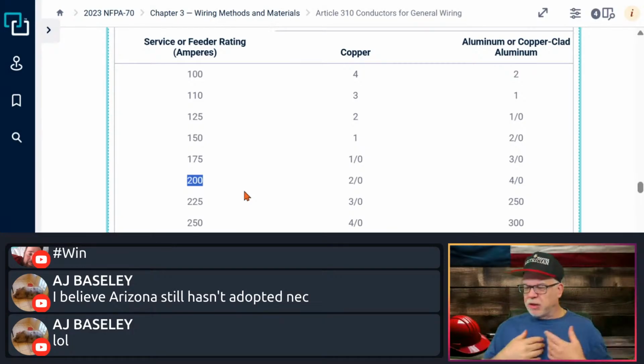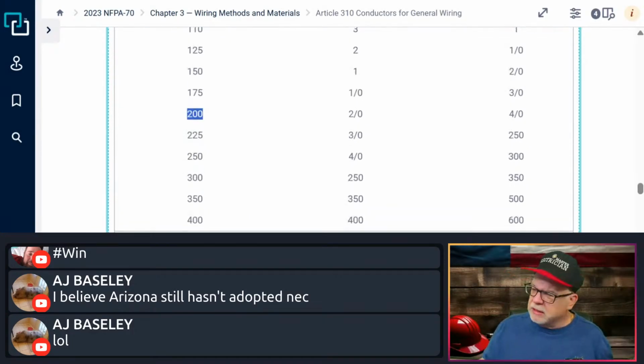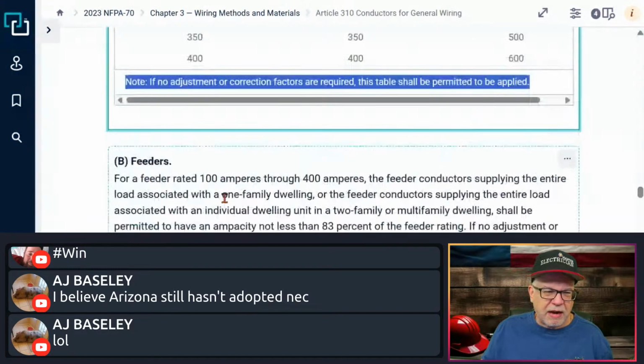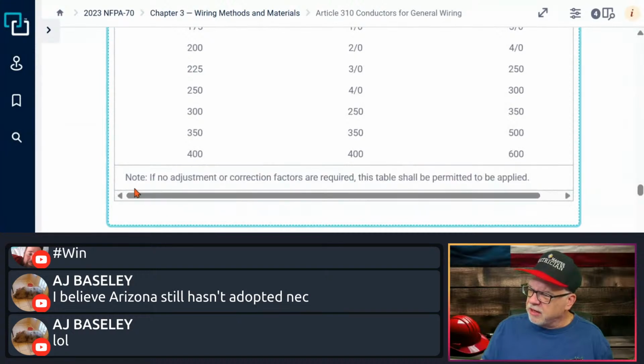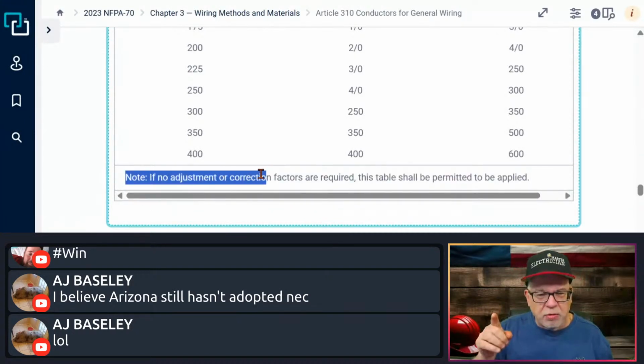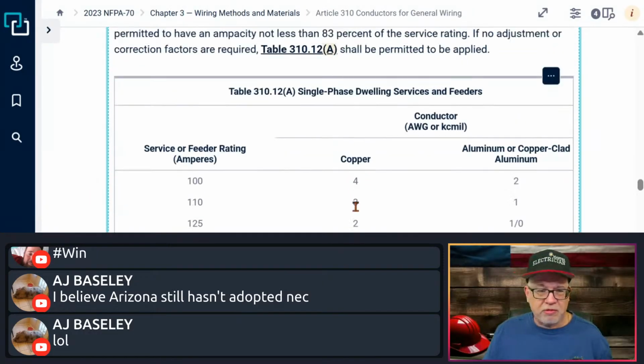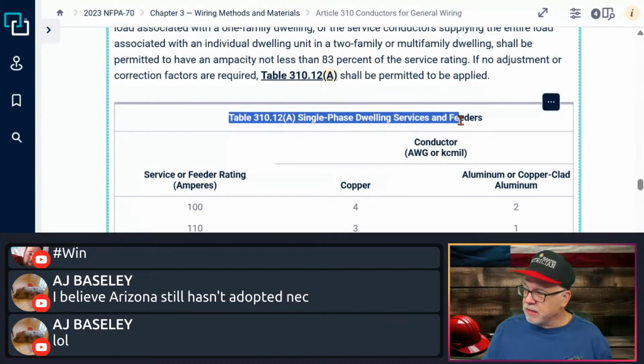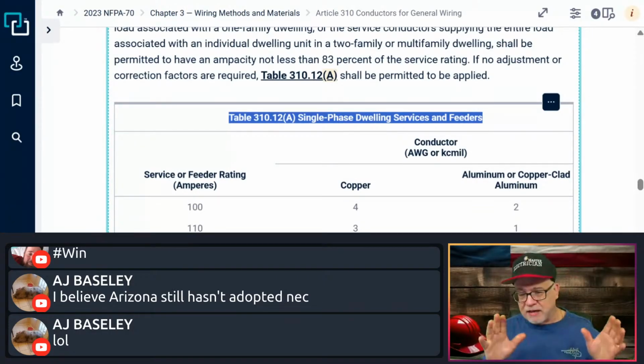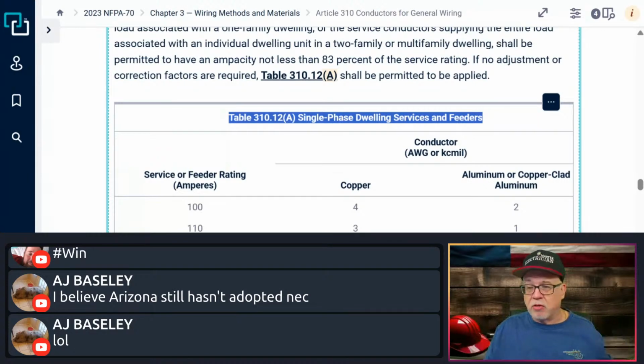Now, if you have to do an adjustment or correction, note, this was my code proposal a couple years ago to clarify this, because there was so much confusion in here that I wanted to make it clear. You can only use this table if there's no adjustment or corrections involved. If there's an ambient temperature issue that needs a correction, or an adjustment for more than 3 current-carrying conductors, then this table is useless. But on an exam, unless they tell you otherwise, you will always use this allowance in 310.12. It is not an exception. This is a rule. This is code.